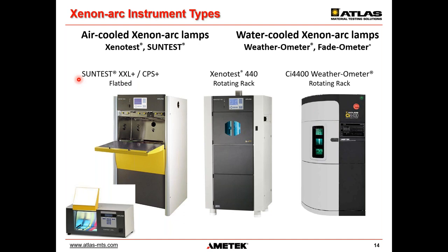The xenon-arc instruments, we really start with them because they are the most important radiation source used in weathering. And there are two different lamp types. There are air-cooled xenon lamps, which are typically lower power lamps for smaller to mid-size instruments. And there are water-cooled xenon arc lamps for the larger test chambers like CI 4400, CI 5000.